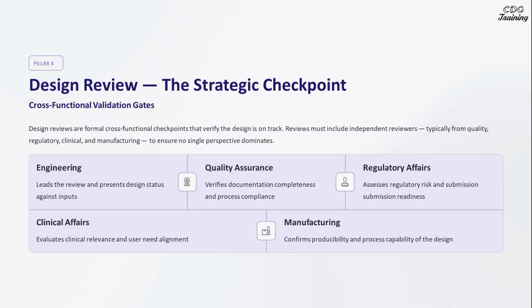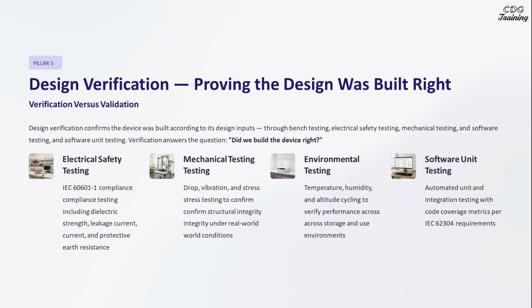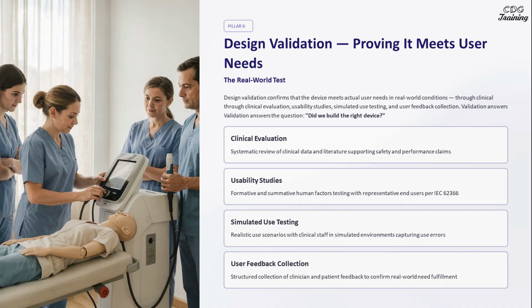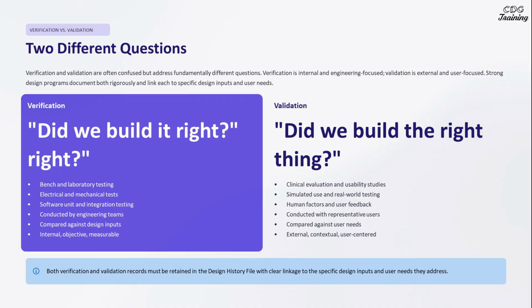Design reviews are strategic checkpoints that verify the design's progress, involving cross-functional teams to ensure alignment. Design verification confirms the device was built right, using various testing methods to ensure compliance with design inputs. Design validation ensures the device meets user needs through real-world testing, confirming it was built correctly. Verification and validation address different questions, focusing on whether the design was built right and if it meets user needs.